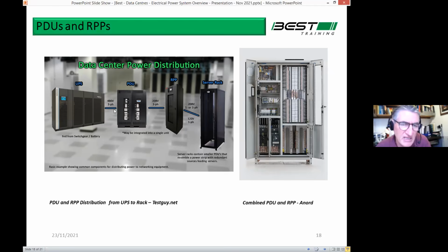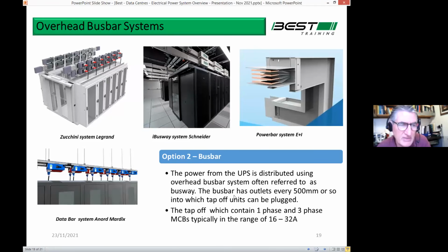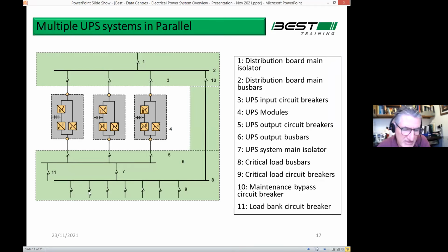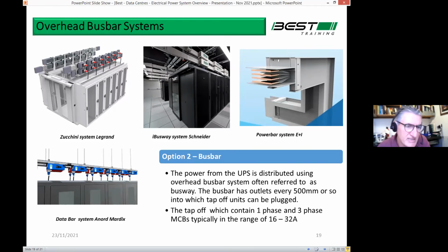You come to the UPS through some sort of a switchgear system or a busbar system, and then power is delivered to the server rack. So I'll show you in the next slide what typically happens. In Ireland, the most common solution is to run the power from the UPS system. Just to go back, to show you where we're talking about, from these circuit breakers here, item 9, each one of those would feed a busbar system. And the busbar system looks something like this, sitting above the server racks here.